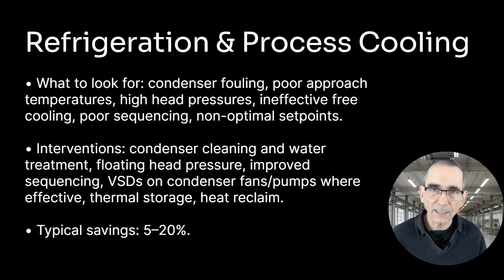Then we look at refrigeration and process cooling. You can look for things like condenser fouling, especially with systems with cooling towers, and poor approach temperatures, for example your condenser water return temperature being too high. High head pressures in the refrigeration system, again, probably signify too high a temperature somewhere. Also look at ineffective use of free cooling and economy cycles, where sometimes you can use outside air effectively, or capture heat or cooling from another process, poor sequencing, and non-optimal set points.